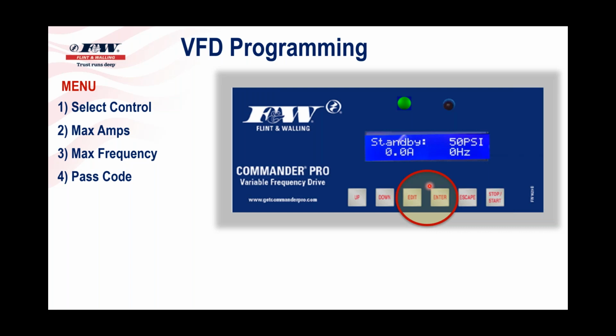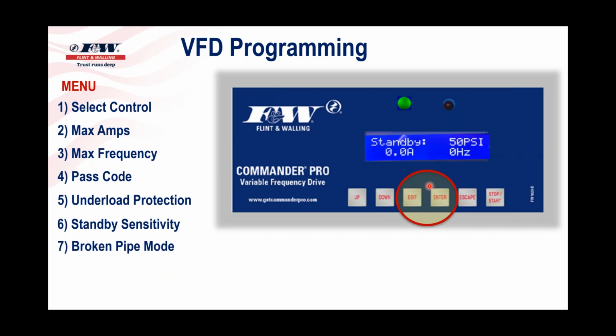Be careful who all you share that with, but that's the back door to get into a Flint and Walling drive. Just plug in that zip code and voila, you're in. So, but there are other menus beyond that. I only today wanted to go through the quick start programming, but some of the other menus you're going to have is your underload protection, which typically comes into play during run-out drives or deadheading situations. We've got standby sensitivity. We've got a broken pipe mode down there.